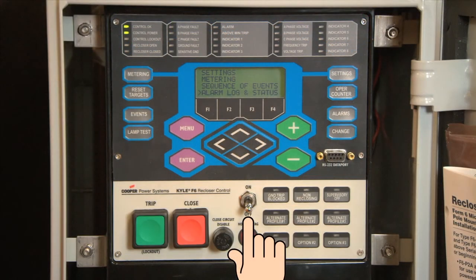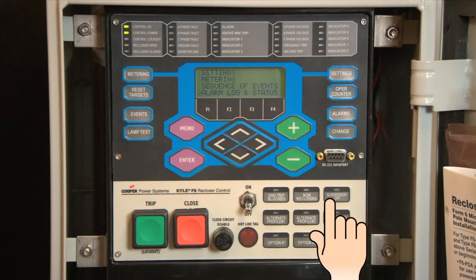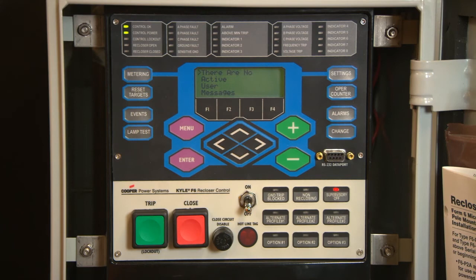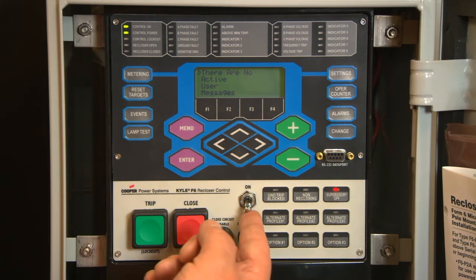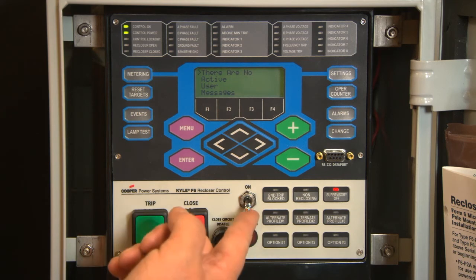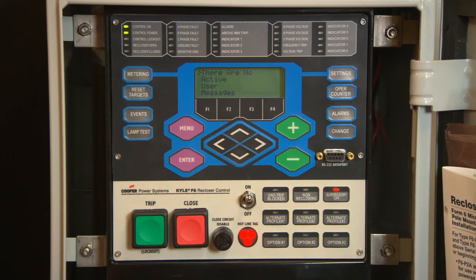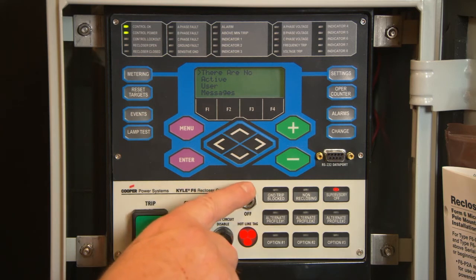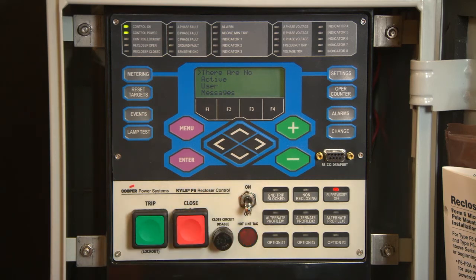Hotline tag is activated from either the operator panel toggle switch, serial communications, or a discrete SCADA function. All sources must be off to deactivate hotline tag. To activate the function from the operator panel, flip the toggle switch up to the on position. The LED indicator illuminates when the function is active. The hotline tag function may only be reset by the source which initiates it. For example, if hotline tag is activated at the operator panel, the reset function is only possible at the operator panel and not via SCADA command.